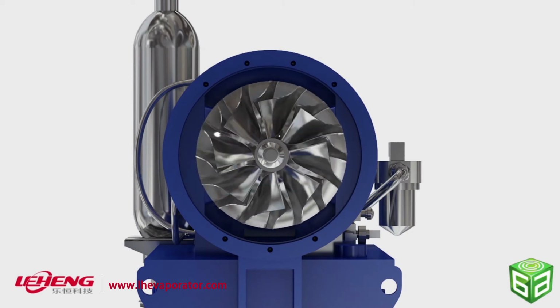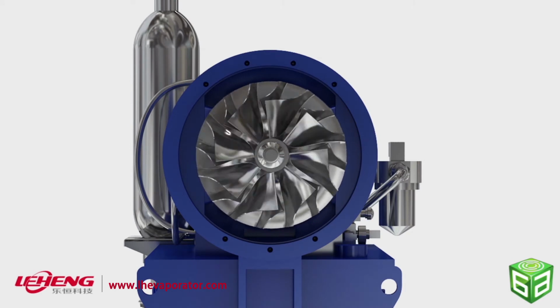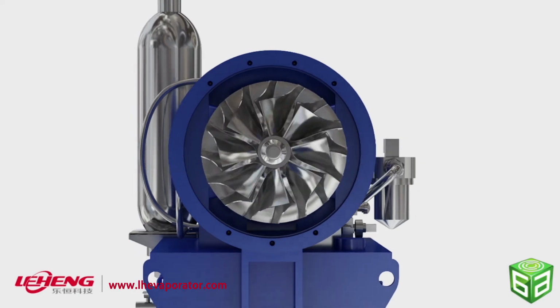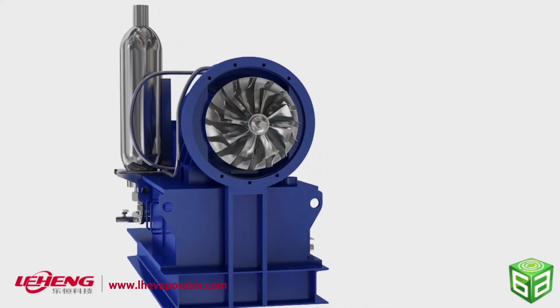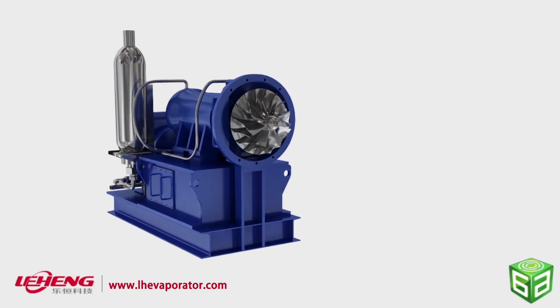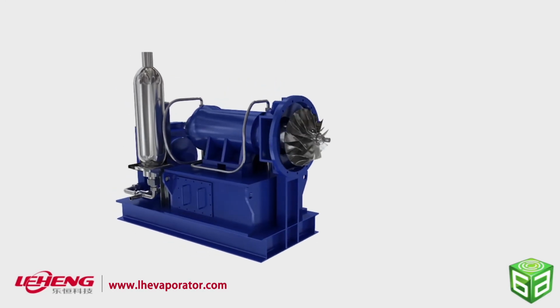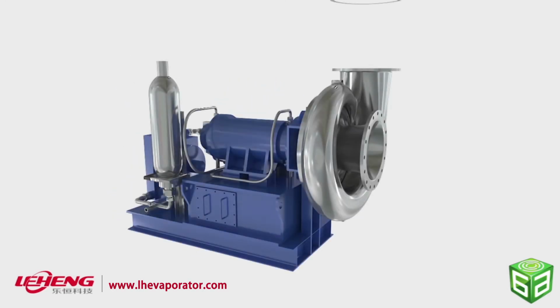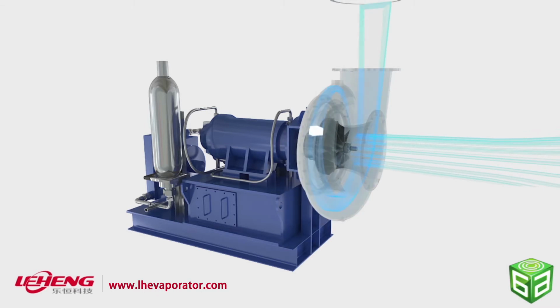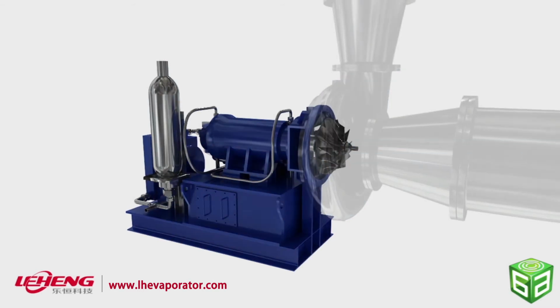The direct drive centrifugal compressor has unique characteristics like compact structure, less vibration, high pressure ratio, better efficiency, and convenient maintenance. The high-speed rotating impeller increases the temperature and pressure of the steam. Pressurized steam then circulates back into the evaporation system from the compressor outlet.